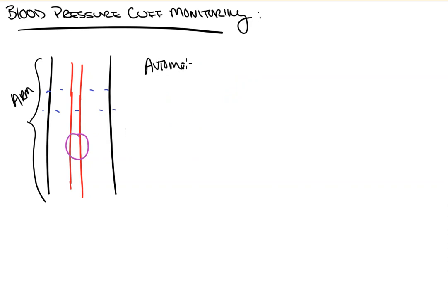So our automated cuffs, like we said, conceptually the same, they're going to occlude the arterial blood flow in a given region. But machines can't auscultate, but rather they sense vibrations. This is referred to as oscillometric monitoring. And people have been asked about this on their oral boards. So, like we said, while the cuff is inflated and blood begins to flow again while it's turbulent, it starts to create a sound. And hopefully we remember from basic physics that sounds are the results of vibrations, and that vibrations are what the machine, in this case, is looking at.